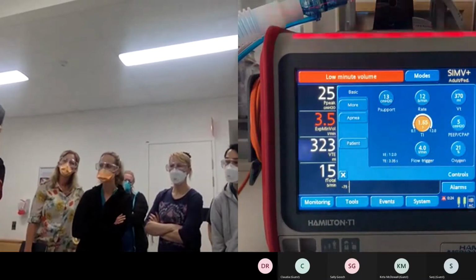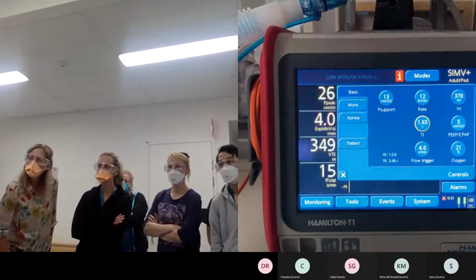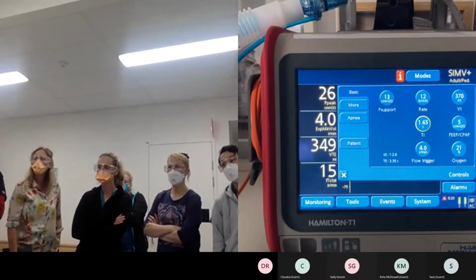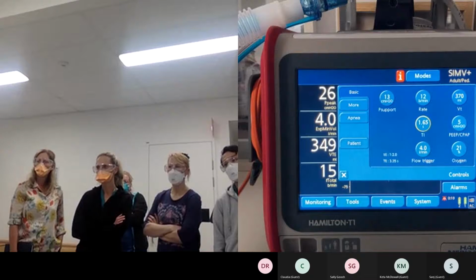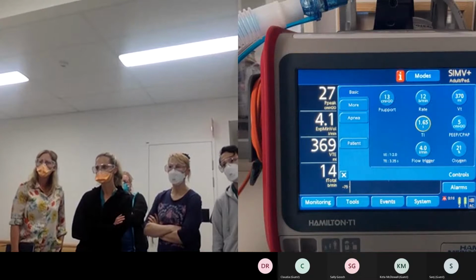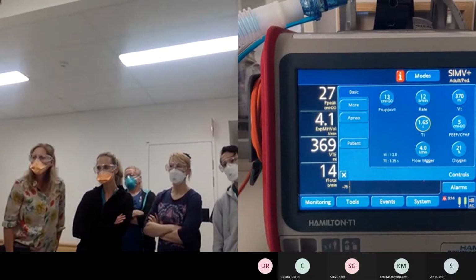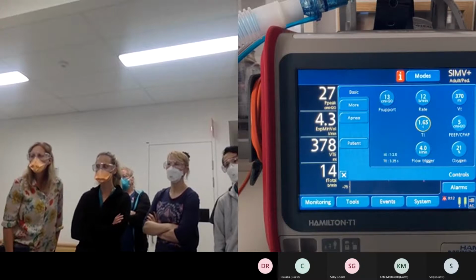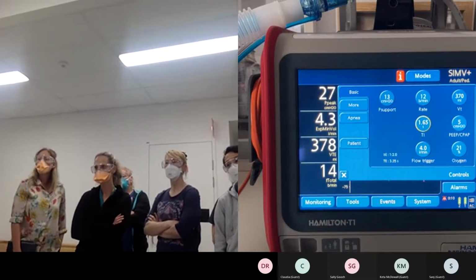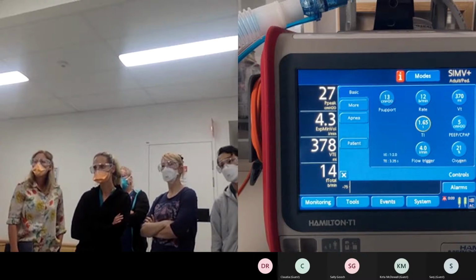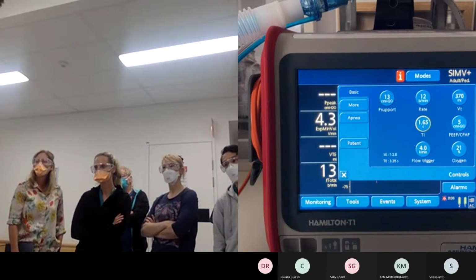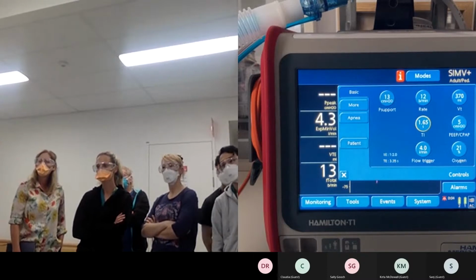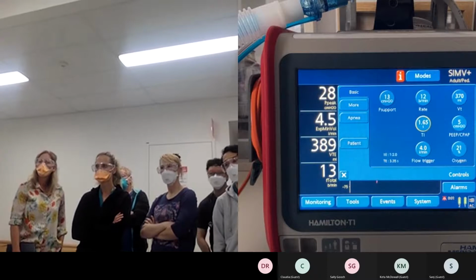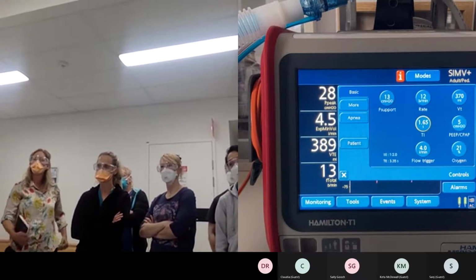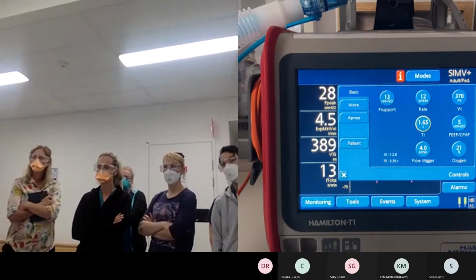I'll just show the guys here. So in SIMV setting, you have the option to adjust the I time, and down there you have your IE ratio. So obviously as you increase your I time, that's going to decrease your IE ratio. And as well, you can adjust your resp rate as well, which will influence that too. So it's a combination of I time and resp rate, which may be slightly different than some ventilators that we may be used to.